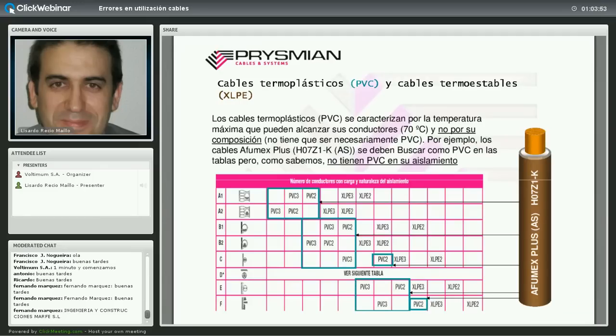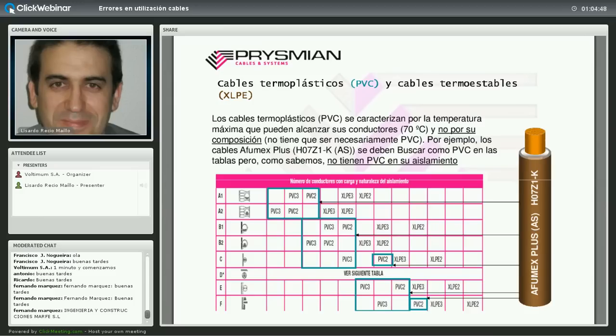Cuando se publicó esta tabla, que viene de la IEC 60364-5-523 y está en España en la UNE 20460-5-523 citada en el reglamento ITC-19, apareció también la exigencia de cables de alta seguridad, la familia AFUMEX. Una novedad era que estos cables son libres de halógenos, por lo que la gente miraba la columna XLPE para sacar intensidades admisibles. Pero esto es un error: el cable AFUMEX de 750 V tiene aislamiento de poliolefinas que soporta 70 grados en régimen permanente, por lo que corresponde a la columna PVC.